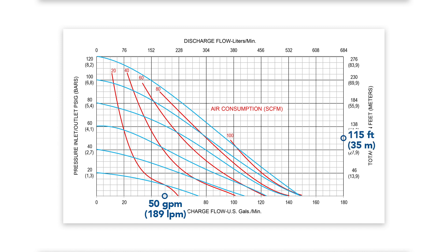To find out how well the AODD pump will perform, utilize the performance curve by finding the 50 gallons per minute along the horizontal axis, then follow the line up to the 115 feet of head along the vertical axis.